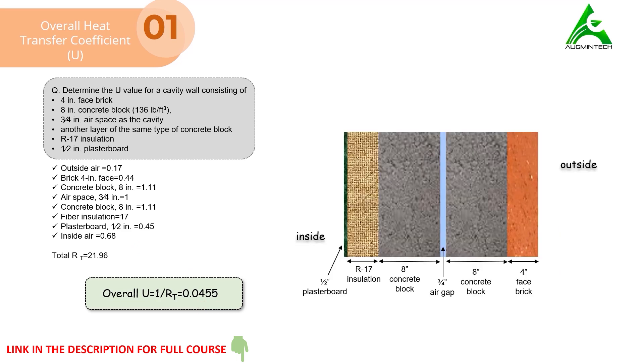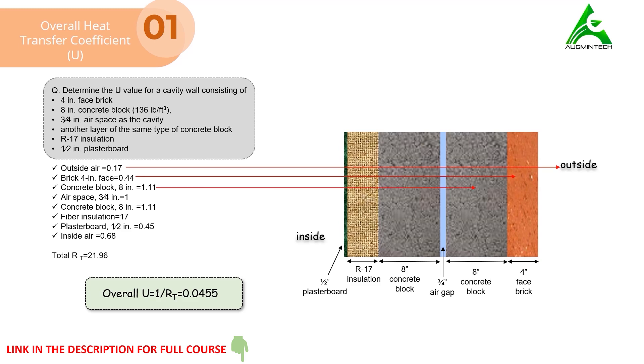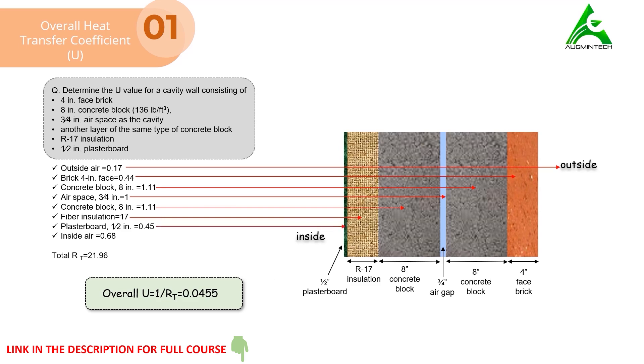The resistance values found for each component are: outside air = 0.17, 4-inch face brick = 0.44, concrete block = 1.11, air space = 1.00, second concrete block = 1.11, insulation = 17, plasterboard = 0.45, and inside air = 0.68. Now that we know how to calculate the overall heat transfer coefficient, this lecture is over. Thank you and see you again in the next one.